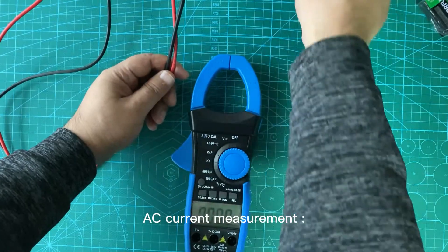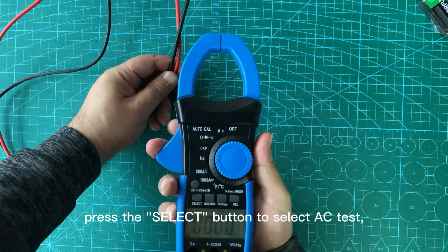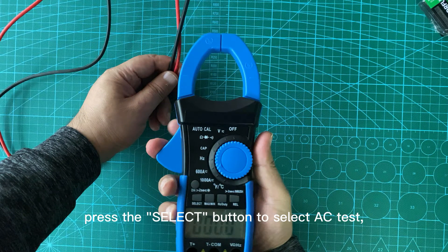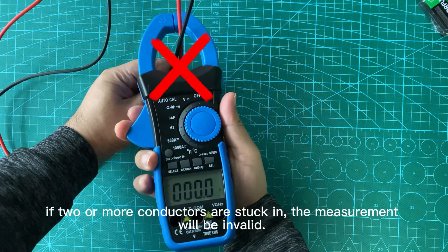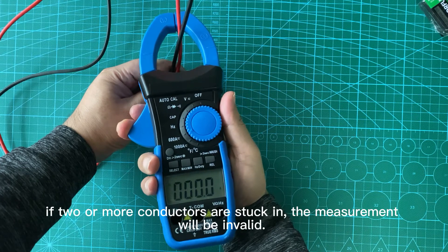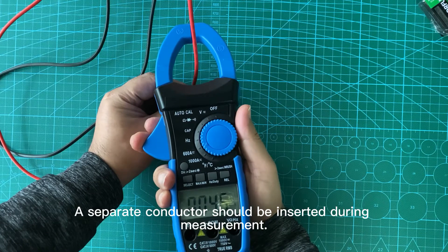AC current measurement: Set the rotary switch to the 600A position. Press the select button to select AC test. Press the trigger to open the jaw. If two or more conductors are clamped, the measurement will be invalid. A separate conductor should be inserted during measurement.